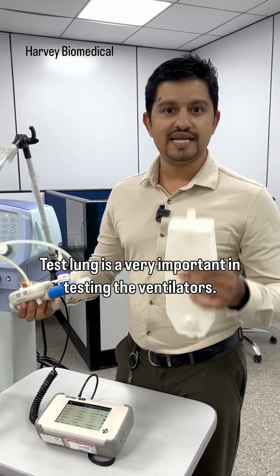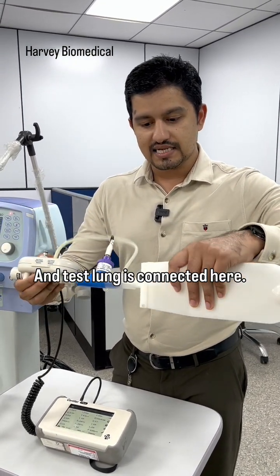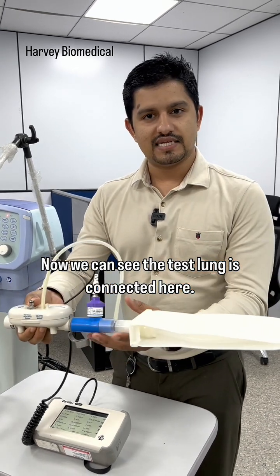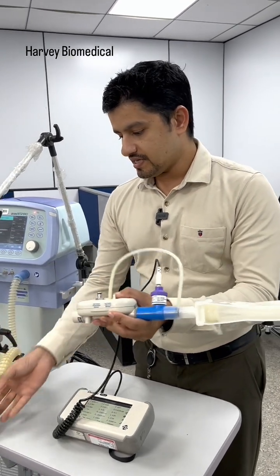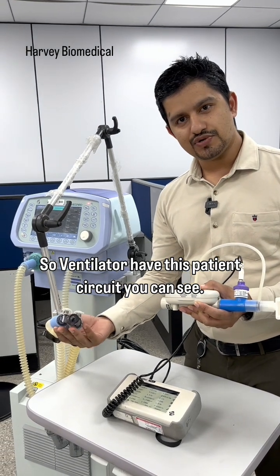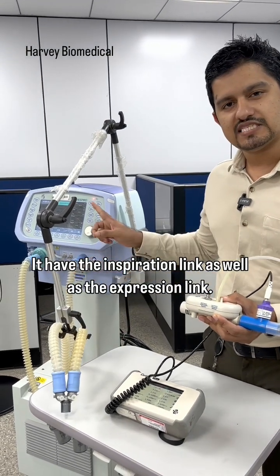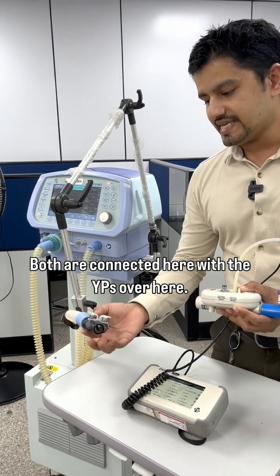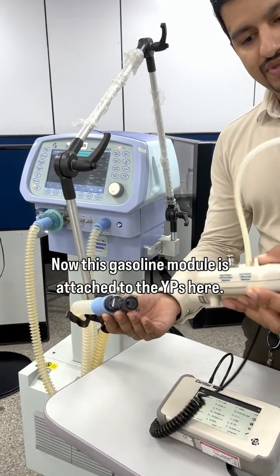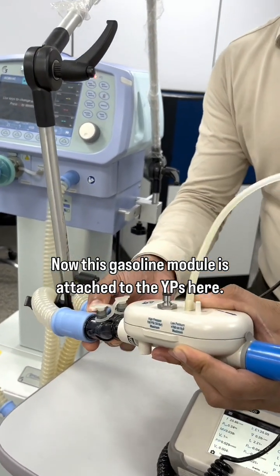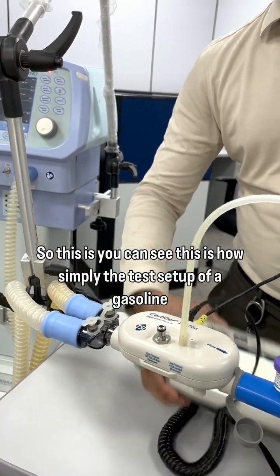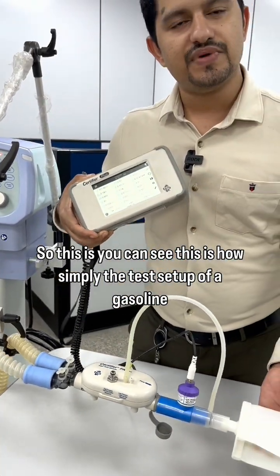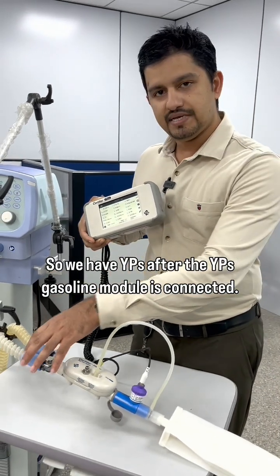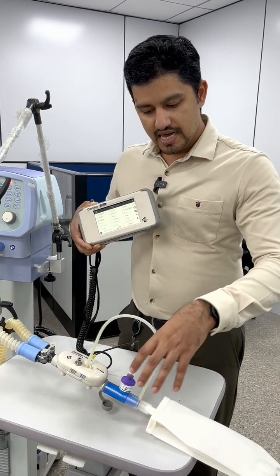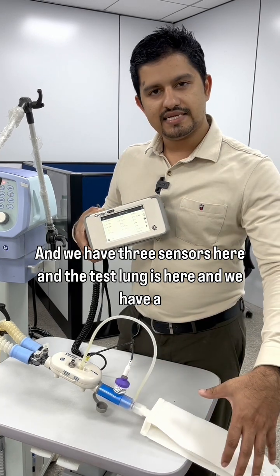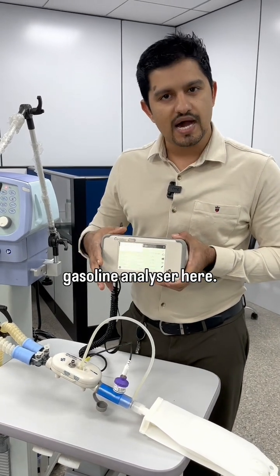Now we have a test lung, which is used to test the ventilator. Test lungs are very important in testing ventilators, and the test lung is connected here. Now how do we connect this with the ventilator? The ventilator has this patient circuit, you can see. It has the inspiration limb as well as the expiration limb. Both are connected here with a Y-piece. Now this gas flow module is attached to the Y-piece here. So this is how simply the test setup of a gas flow analyzer looks. After the Y-piece, the gas flow module is connected, and we have three sensors here, and the test lung is here, and we have a gas flow analyzer here.